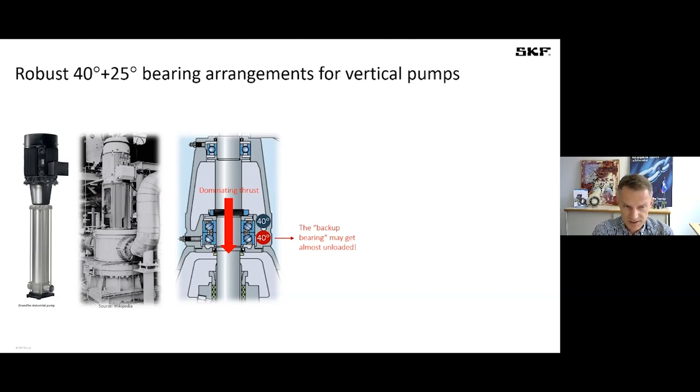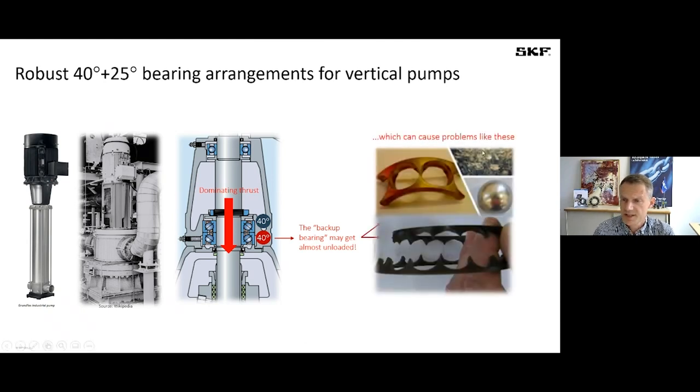You see some vertical pumps, typical ones on the left side, and in the middle you see a typical bearing arrangement, this time with two single angular contact ball bearings, and normally 40 degree bearings with 40 degree contact angle are used here. But in many cases you have then either due to the gravity force or other forces a dominating thrust load, and it might happen that one of these bearings that we call the backup bearing gets unloaded because the other one is loaded so much and there is movement displacement in the bearing set. Then this bearing gets unloaded and can get damaged. So if you see damages like those on broken cages or worn cages or balls that have smearing marks, you might have this problem of unloaded or too loaded backup bearing.